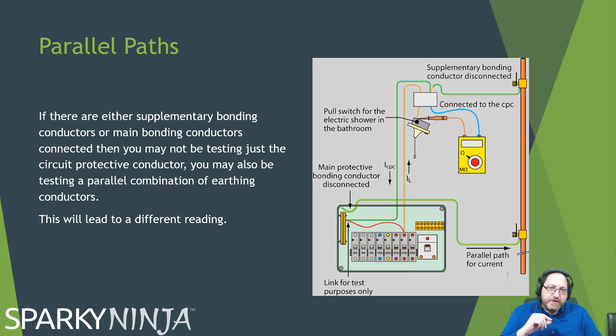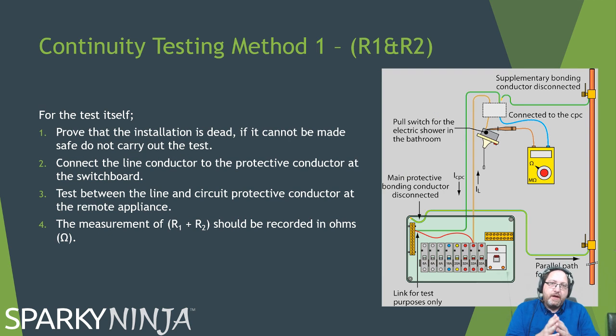Two methods of measuring continuity. Method 1 is an R1 plus R2 test. Method 1 has R1. That's the good way of measuring it. So here, we're going to ensure the equipment is dead. We're going to prove it's dead. And what we're going to do is disconnect all the parallels of the circuit. This illustration is a bit rubbish really.